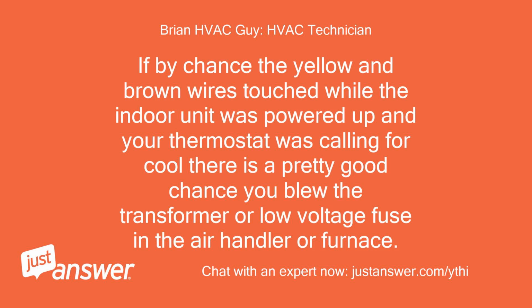If by chance the yellow and brown wires touched while the indoor unit was powered up and your thermostat was calling for cool, there is a pretty good chance you blew the transformer or low voltage fuse in the air handler or furnace.